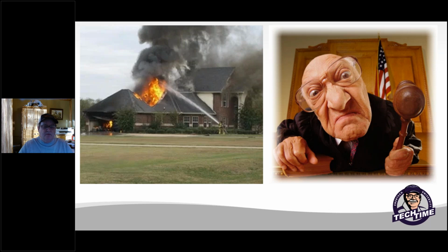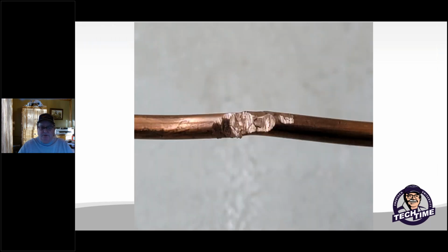Well, here I have a leak that was found in a copper cap tube. This was an external equalizer line, which is kind of typical. If you read your manuals, they always tell you to look at all the piping, all your wiring, make sure nothing is touching, make sure nothing is rubbing. And some of that stuff gets shifted or moved from transportation.